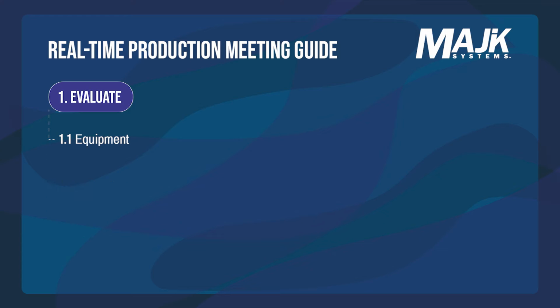In the equipment evaluation, you'll want to answer key questions such as what equipment is going down and what are the main reasons for downtime. How are the key performance indicators such as OEE, MTBF, and MTTR tracking over time? Are there patterns in the data that will allow us to identify issues before they happen or spot wear on a machine? Evaluating data should start before the meeting.